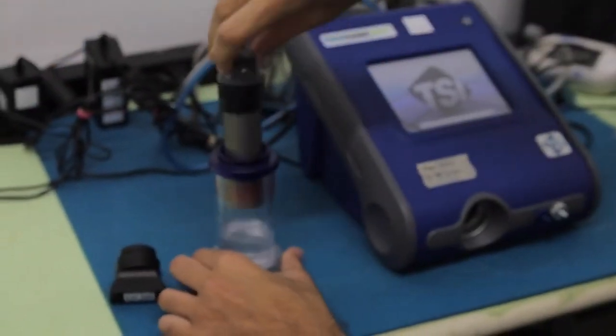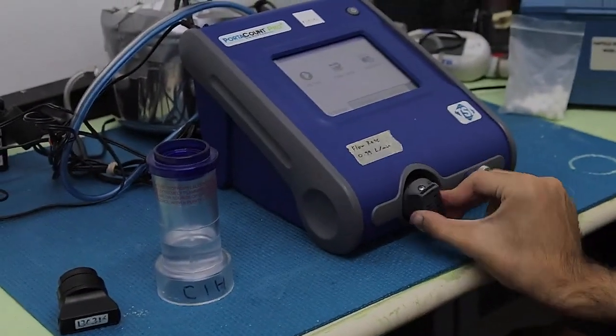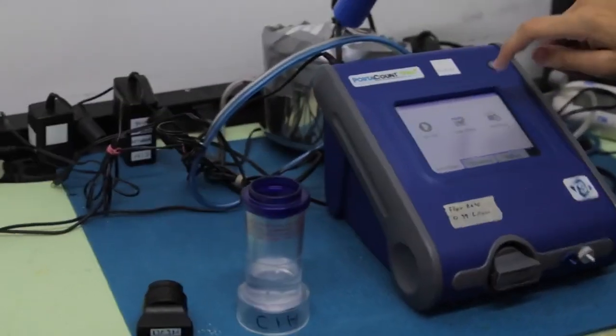Twist the cap to the left and pull the wick out of the PortaCount. Next, you're going to reach over to the alcohol cartridge and pull out the testing wick and insert the wick into the slot. Make sure to turn it until you feel it click into place. Once you're done, tap Daily Check on the screen.